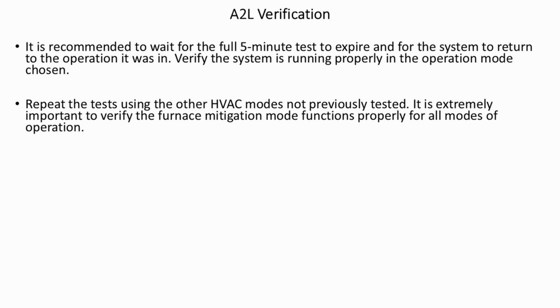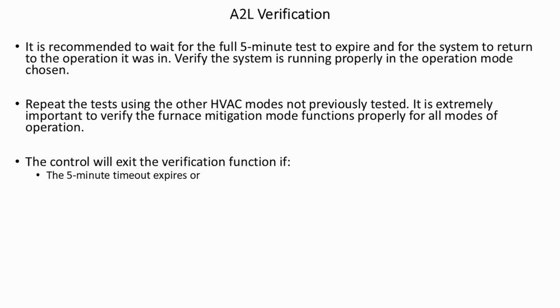Repeat the test using the other HVAC modes not previously tested. It is extremely important to verify the furnace mitigation mode functions properly for all modes of operation. The control will exit the verification function if the 5-minute timeout expires, or an alarm or fault is detected, or the user turns off the A2L function verification.